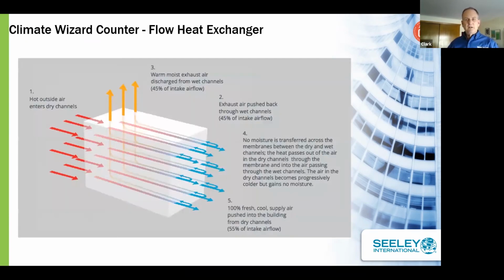So you might ask, how do we do that? Well, we have a plate heat exchanger. It's a cross flow heat exchanger where we take the outdoor ambient air and run it through this heat exchanger, which consists of wet and dry sheets. And we cool the air down. We put water in at the top, and that water flows through the wet sheets from the top to the bottom. Then we have a damper that puts a back pressure on the backside of the heat exchanger that forces some of this cool air back through, which cools the hot air down. And then the orange arrows are the exhaust air that goes out of the unit.